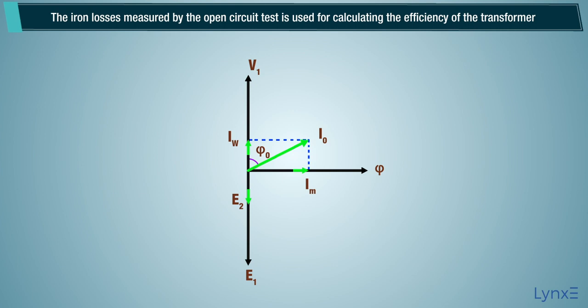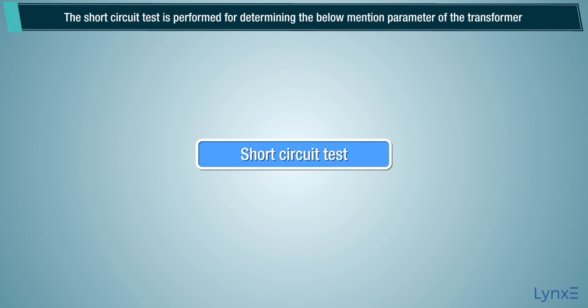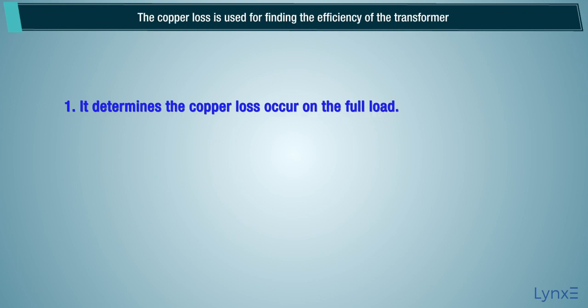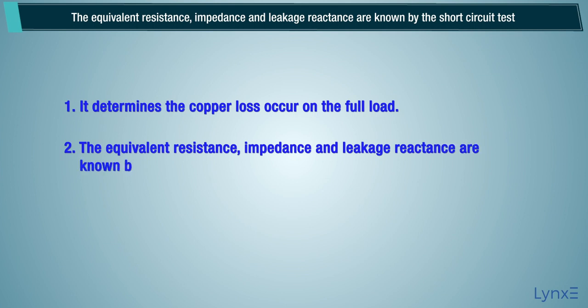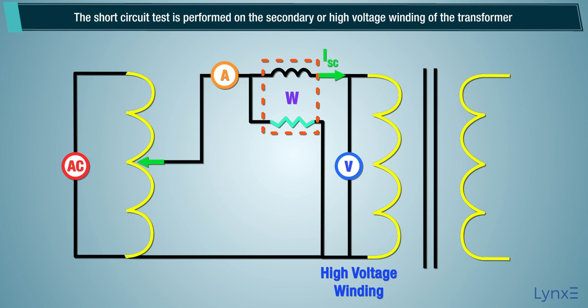The short circuit test is performed for determining the below-mentioned parameters of the transformer. It determines the copper loss occurring at full load. The copper loss is used for finding the efficiency of the transformer. The equivalent resistance, impedance, and leakage reactance are known by the short circuit test. The short circuit test is performed on the secondary or high voltage winding of the transformer.